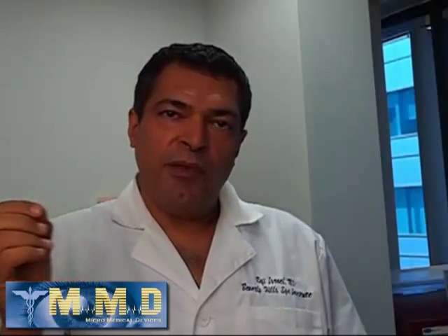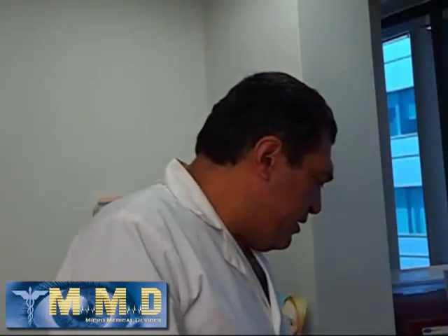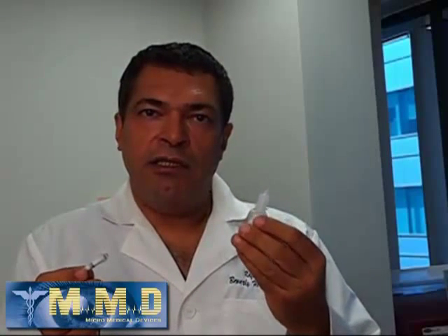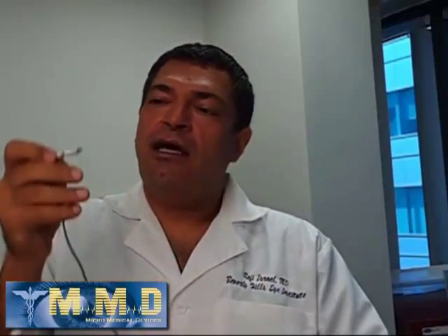The other problem that I've seen some techs have is the way that they fill the water and the way they touch the cornea. If you fill the chamber of the easy immersion tip properly, you should only have just about the meniscus of water be transferred to the patient. Now, a lot of times I've seen some offices not use BSS, and they use eye wash or other material that have soap in it. If you do that, then the surface tension is decreased and the water seeps out a lot easier. So you want to make sure that you use the proper solution so the surface tension will hold the meniscus.